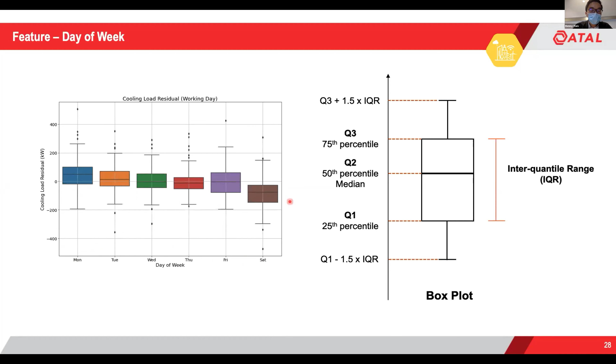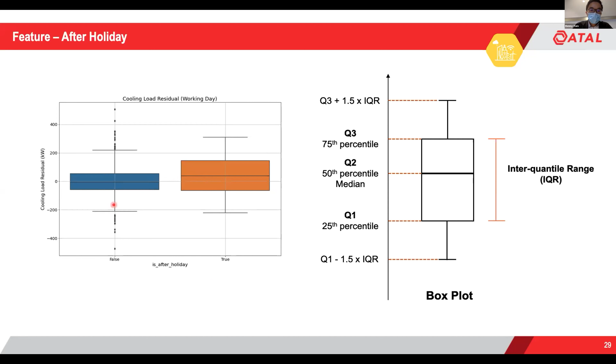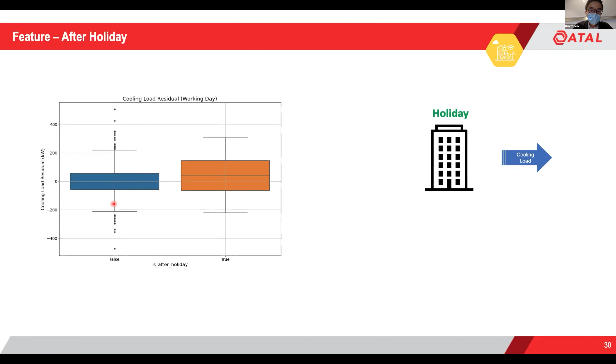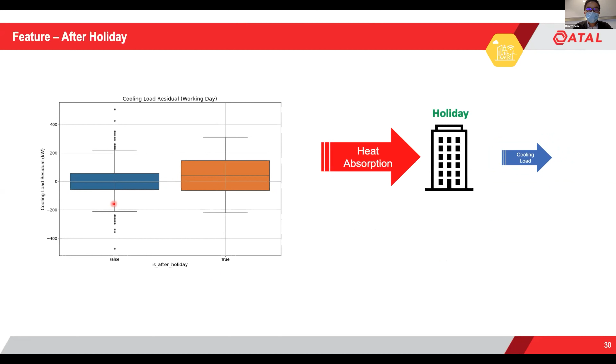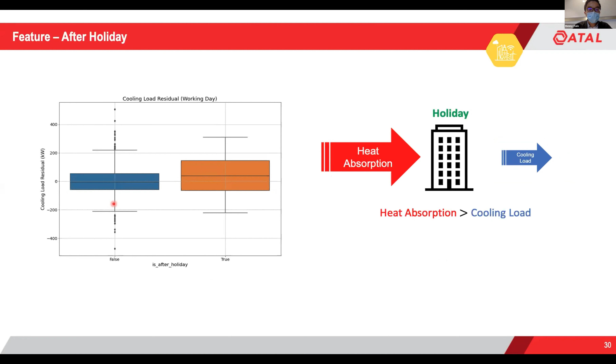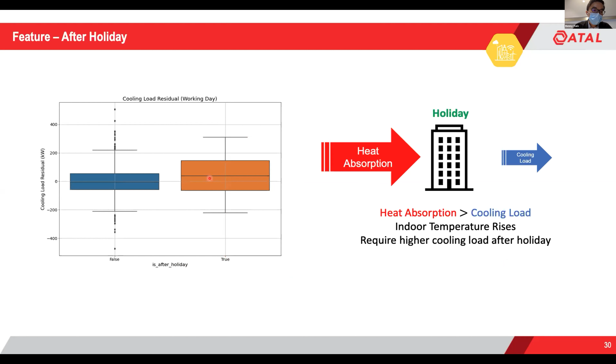Finally, we find something interesting: if it's a working day right after a holiday, the cooling load is slightly greater than normal working days. Why is that? Here's our interpretation. During the holiday, the cooling load is very small, as you already know from the previous slides. But you still have heat absorption from the surroundings, like the sun and other external factors. So you get an inequality where heat absorption is greater than the cooling load, your office temperature rises, and therefore you require more cooling load after the holidays. We think this is also a good feature, although the median difference isn't very large.